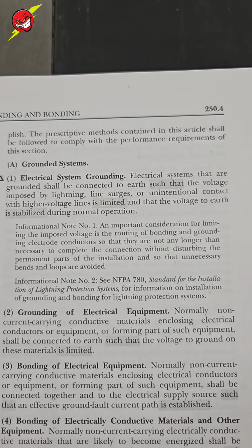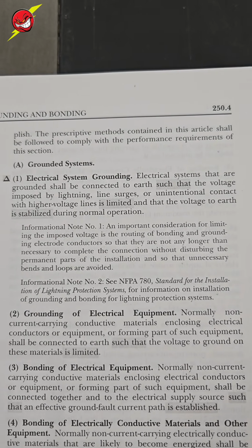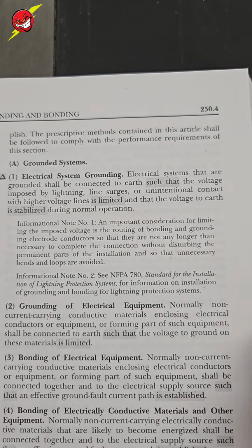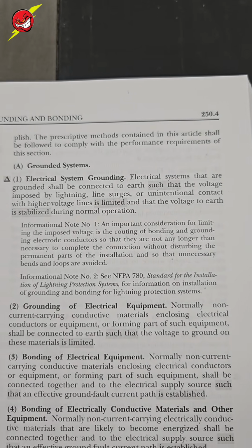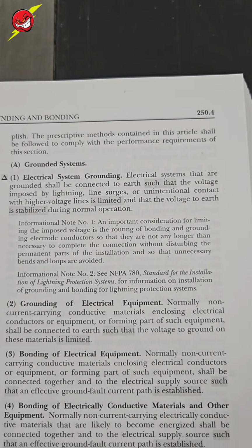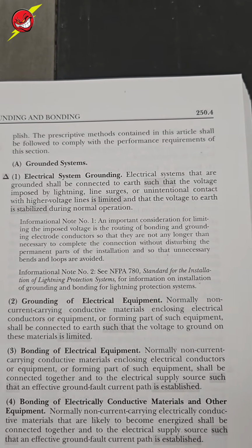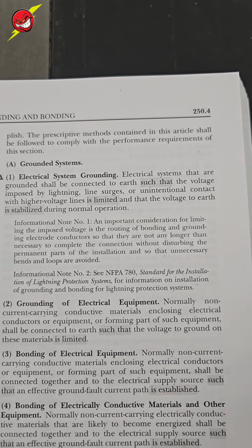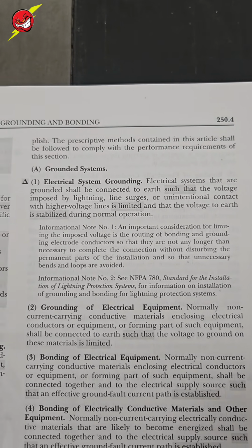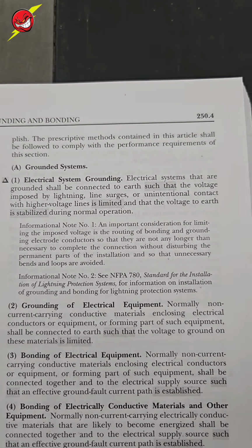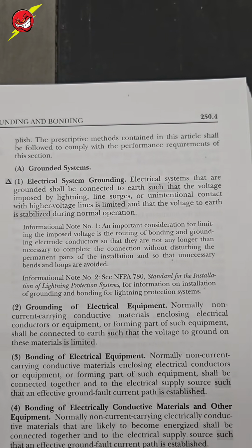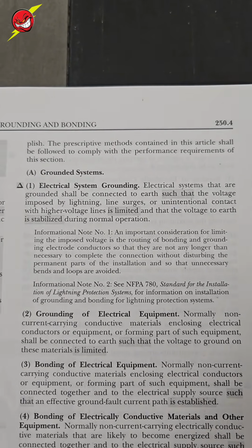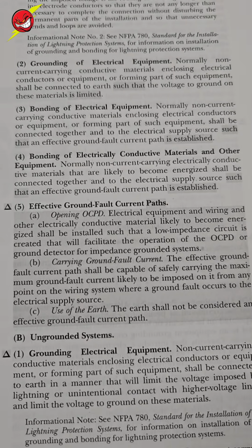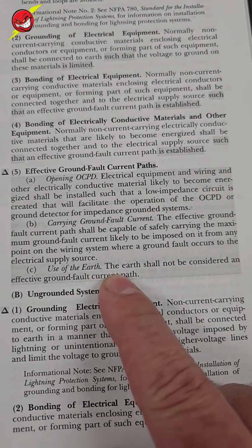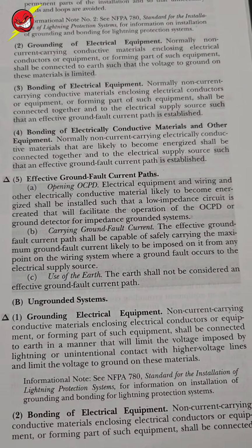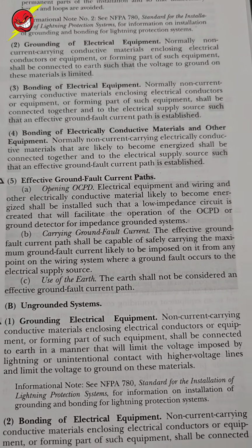Article 250.4 is your general requirements for grounding and bonding. 250.4A1 tells us exactly why we connect to the earth. Right, here's your lightning protection. Notice nowhere in here does it state tripping a breaker or blowing a fuse or anything like that. We do not connect to the earth and establish a connection to the earth to clear a fault. It will not blow a fuse or trip a circuit breaker. Keep reading. Right there, it even states the earth shall not be considered an effective ground fault current path.